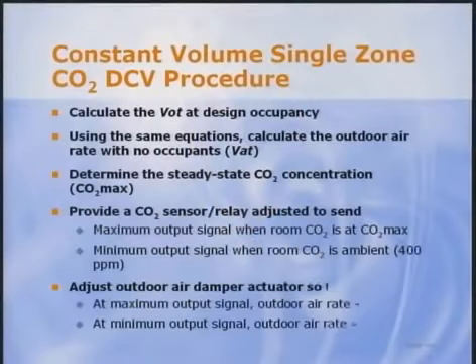The final step is made in the field in conjunction with the air balancer. The damper actuator or linkage would be adjusted so that at the maximum CO2 sensor output, such as 20 milliamps, the system would deliver the design outdoor air rate, VOT. At the minimum signal, 4 milliamps, the damper position is adjusted to provide VAT.